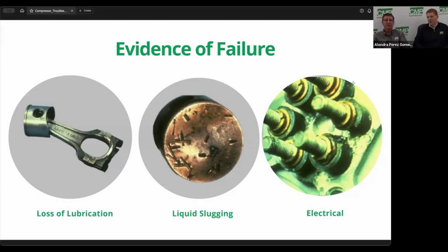Some of your mechanics are maybe scared of doing a valve plate job or don't want to take a compressor apart. But the best thing you can do is to learn to take that valve plate off and change the valve plate on it. Those are very changeable, a lot easier than changing a compressor. Yeah. But the hottest head's going to be the one giving you the problem. And this is a tip, and I didn't know this actually when I was in the field, because I was in the field doing supermarket, changing compressors, installing, service, startup, all that stuff. But I didn't know going around and checking the temperature of each head. If it's 6-cylinder, you check the temperature of each one. If one is way hotter, just like Horace said there, that is a problem. I think in the Bitzer manual, they say 30 degrees differential. You definitely want to check that.